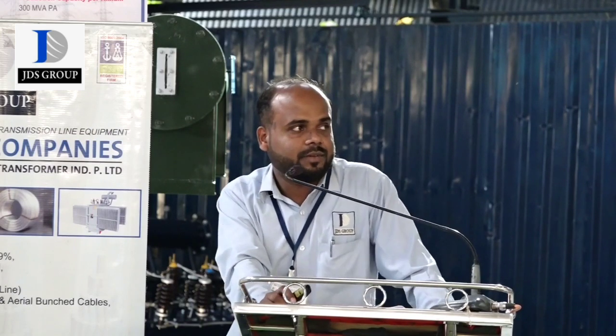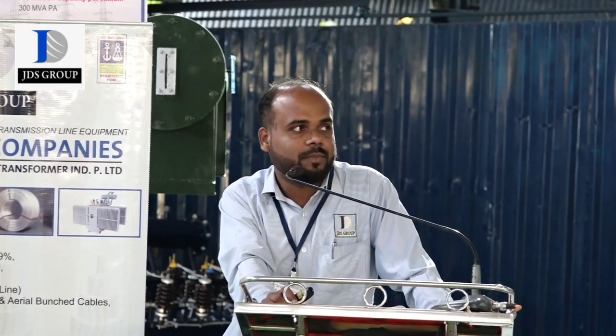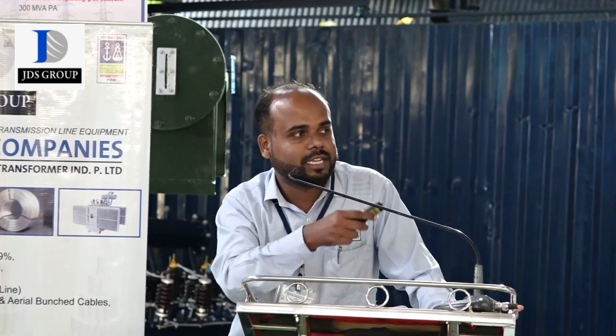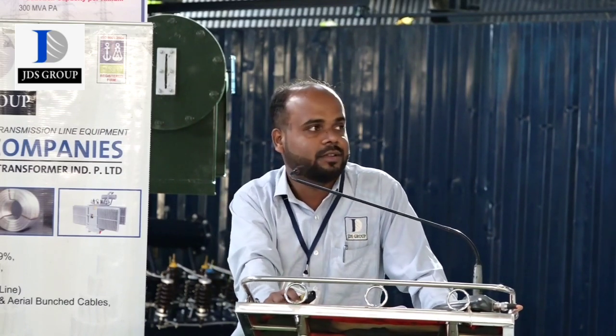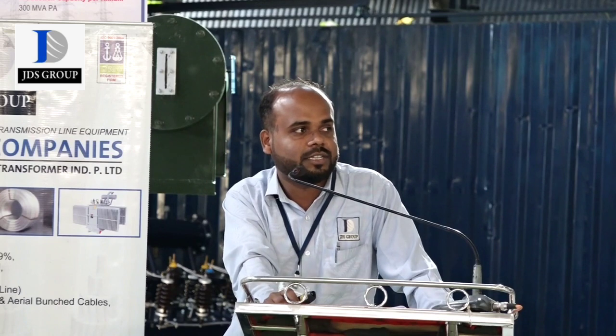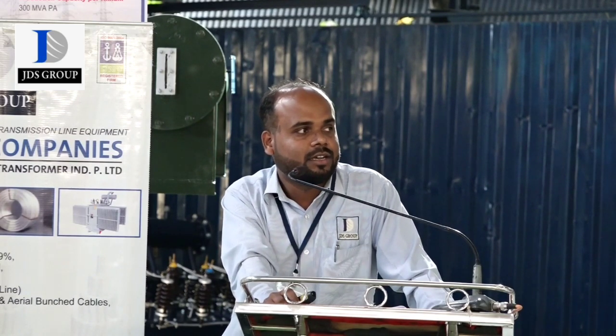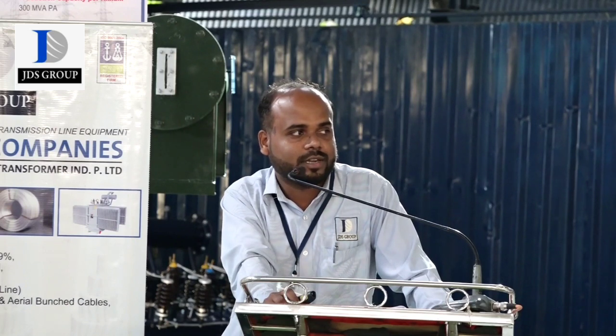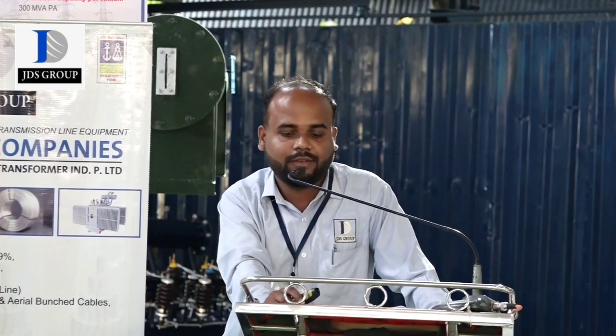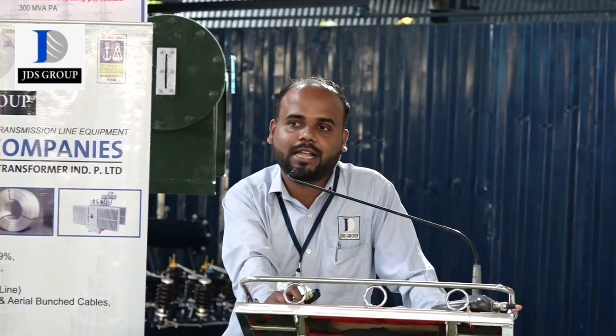For testing of the transformer we follow standard IS 1180 part 1 and IS 2026. So these are the main routine tests we conduct in each and every transformer: winding resistance, insulation resistance, DDF test and high voltage test, no load test, load loss, vector group, oil BDV, and if the OLTC is attached, we perform duty cycle test on OLTC.